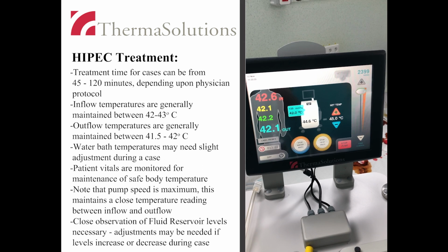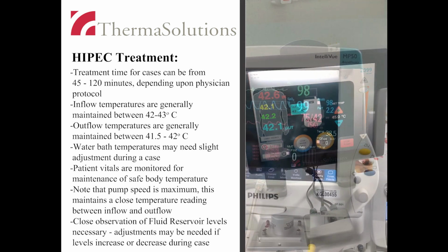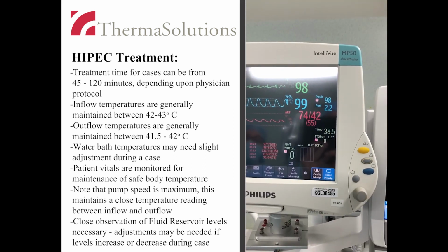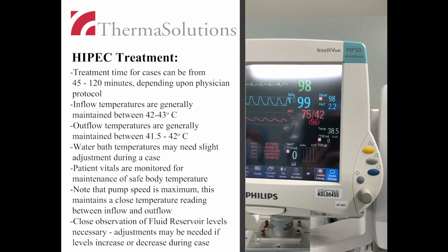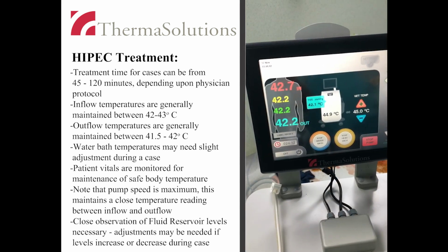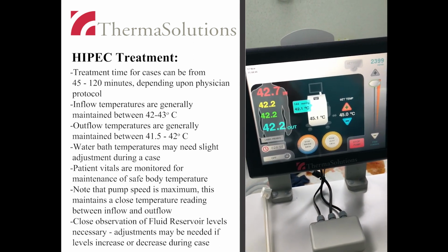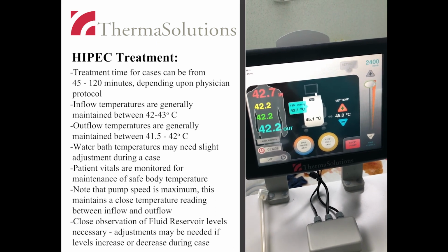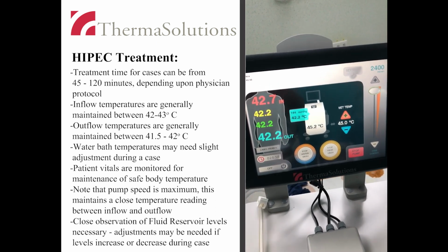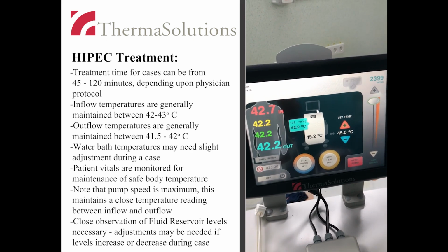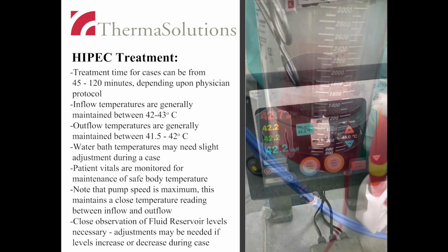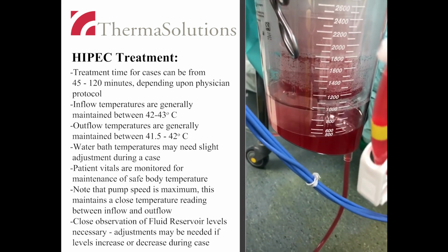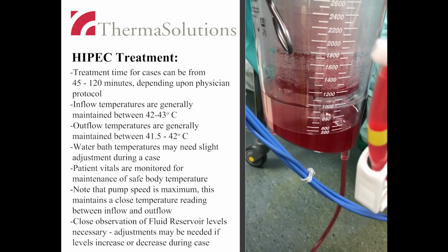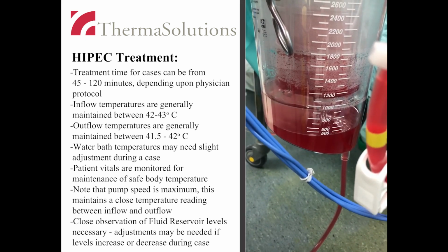Water bath temperatures may need adjustment during the case. Patient vitals are monitored for maintenance of safe core body temperature. Note that a higher pump speed will help maintain a minimal temperature difference between inflow and outflow. Close observation of the fluid reservoir levels is necessary. Adjustments to reservoir height, outflow occlusion, and pump speed may be needed if levels increase or decrease during the case.